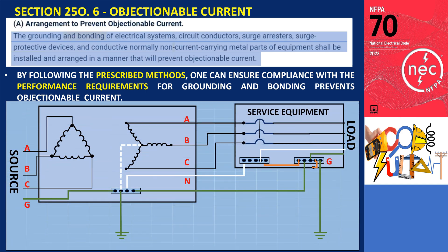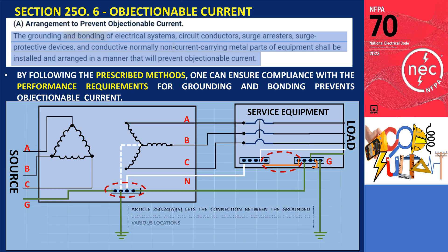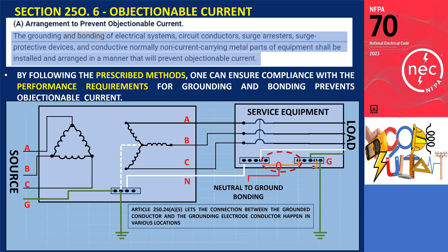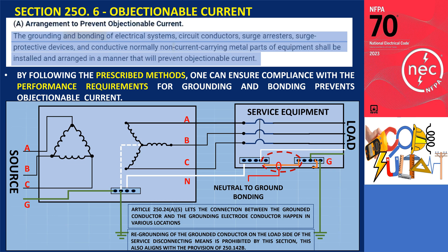Going back to the first example, where multiple bonds of neutral to ground were set up, Article 250.24A5 lets the connection between the grounded conductor and the grounding electrode conductor happen in various locations: on the supply side of the service disconnecting means, or within the enclosure of the service disconnecting means. Additionally, re-grounding of the grounded conductor on the load side of the service disconnecting means is prohibited by this section. This also aligns with the provision of 250.142B.